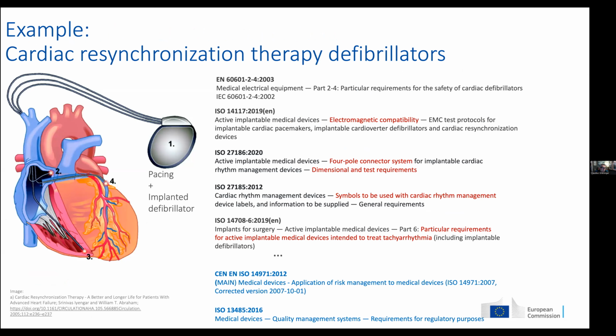And these pacemakers normally nowadays are also implanted defibrillators. What you can see here is all the different standards, not all, some of the relevant standards, there are many more, of course, that you could use for that evaluation: particular requirements of the safety of such defibrillators, electromagnetic compatibility, the 4-pole connector systems, the dimensions, symbols to be used, particular requirements for active implantable medical devices, and then the very basic ones, in a way, very important ones, the risk management system for medical devices and the quality management system for regulatory purposes. Those are very horizontal standards.